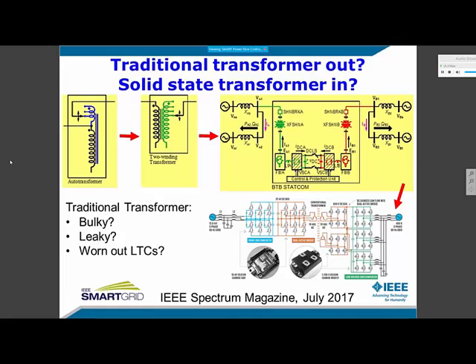However, if we need a galvanic isolation between these two windings, then we use a two-winding transformer, which we call shunt-shunt topology. In this configuration, both windings are high voltage and high current rated. Therefore, its rating is much higher than an autotransformer. But if we need it, we use this higher rating topology, even if it costs more.